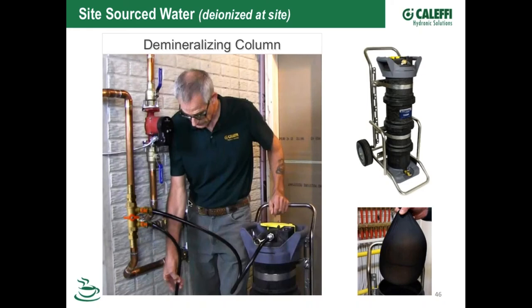Or even a chiller. The other thing that happens is the TDS, which is what those conductivity meters work off of, also rises. As you'll see in the German VDI standard or the Swiss standard, the TDS range that systems tend to stabilize to over time is between 30 and 60 parts per million, or measured in conductivity, 50 to 100 microsiemens per centimeter.